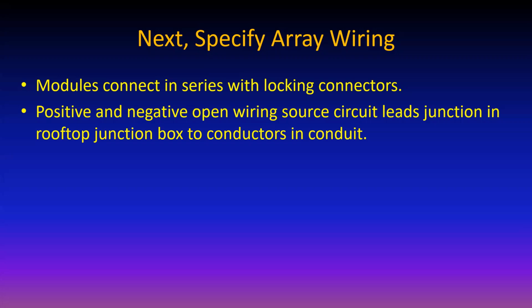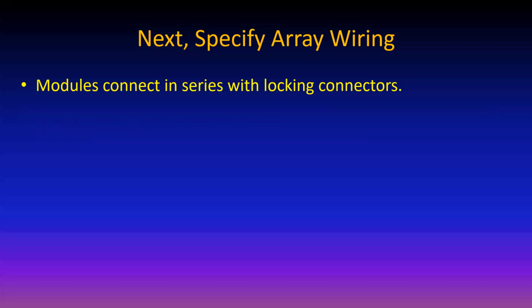When you wire up your string, these are open wiring, by the way. There are 2 types of wiring allowed for open source circuits, and that's PV wire and type USE-2. Mostly right now, the insulation being used is type PV, as in photovoltaic. It's rated for open in the sun exposure. It's got UV resistant insulation, and it saves you the problem of having to run conduit from module to module. Once upon a time, right around 2000, you had to run liquid tight from one module to the next, and boy, that took a long time. No more of that stuff; they got over that in a hurry. Very simple, straightforward connectors, one module to the next, click, click, click, down the string you go, and you're done. Okay.